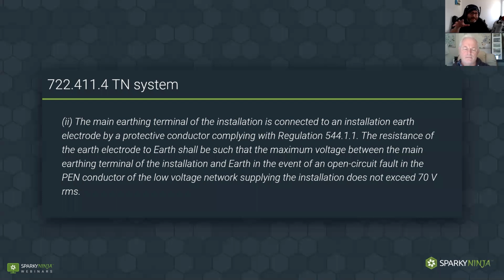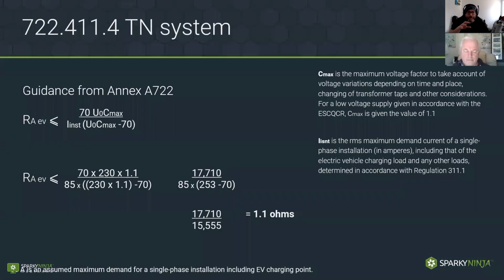The annex has been updated in Amendment 1. So you'll notice in the annex that they've got these little values such as Cmax. This is the formula that's used in the annex, and I've played with it a little bit here. So we've got the RA, the electrode to the electric vehicle point, must be less than or equal to 70 times the U0 times Cmax. And we can see Cmax is a factor given for the maximum voltage factor, considering voltage variations.